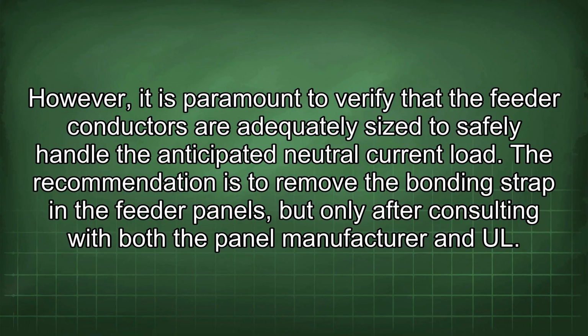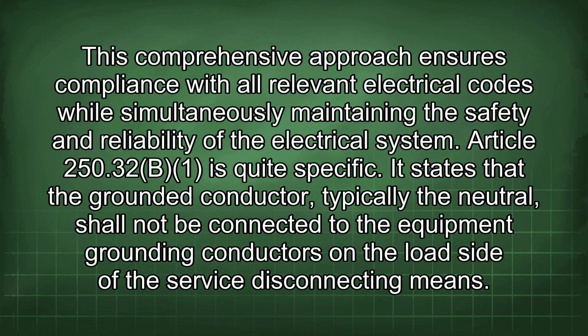The recommendation is to remove the bonding strap in the feeder panels, but only after consulting with both the panel manufacturer and UL. This comprehensive approach ensures compliance with all relevant electrical codes while simultaneously maintaining the safety and reliability of the electrical system.